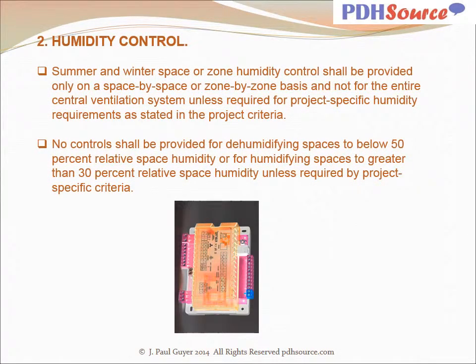Summer and winter space or zone humidity control shall be provided only on a space-by-space or zone-by-zone basis and not for the entire central ventilation system unless required for project-specific humidity requirements as stated in the project criteria. No control shall be provided for dehumidifying spaces to below 50% relative humidity or for humidifying spaces to greater than 30% relative space humidity unless required by project-specific criteria.